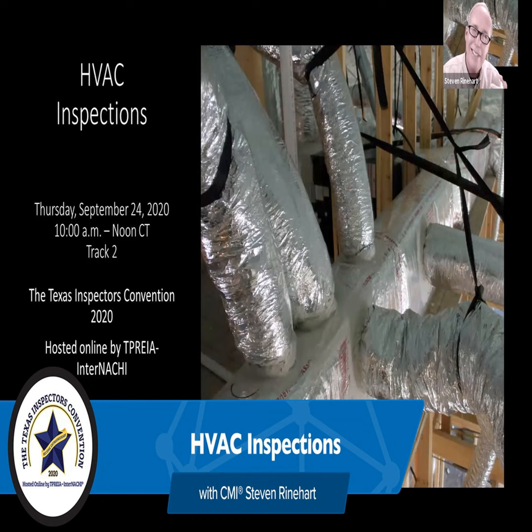Conditions of the conductors, that's the wires going to them. They're limited visibility. They come in usually out of the ceiling. It'd be nice if they all had disconnects. A lot of contractors, if the unit's in the attic, it's about 50-50 on whether or not they have an equipment disconnect in the attic. I personally think there should be. They put them at the outside unit, they should put them in the attic unit. It's just a safe thing to do, and depending on how you read the code, it should have a disconnect.